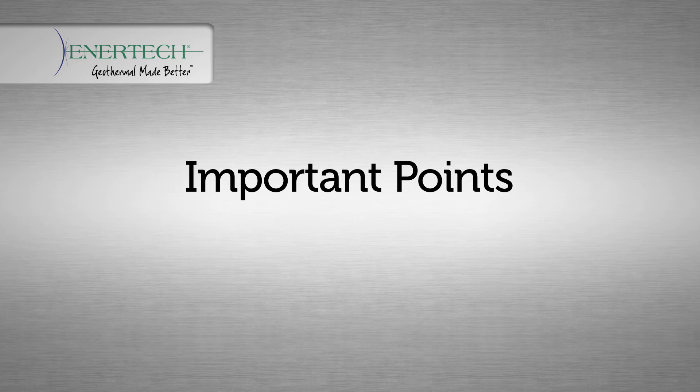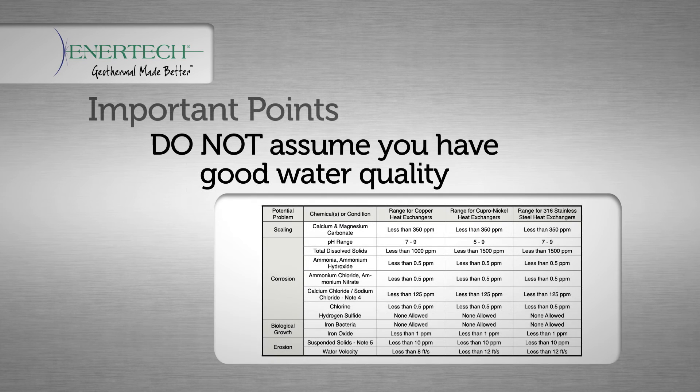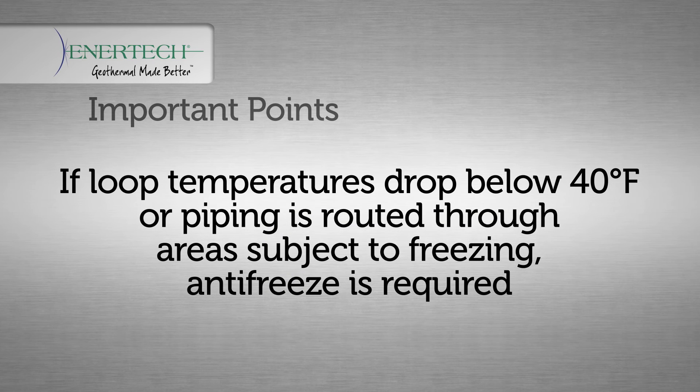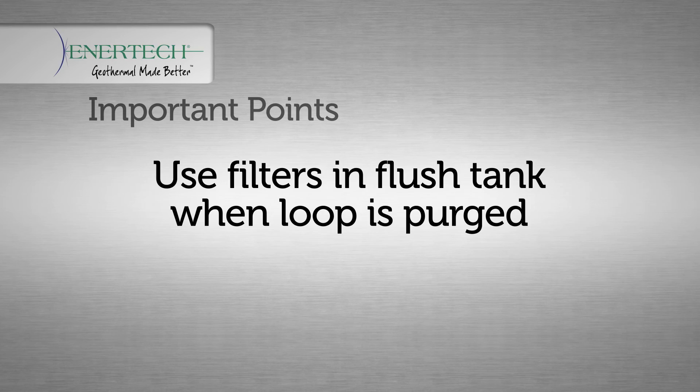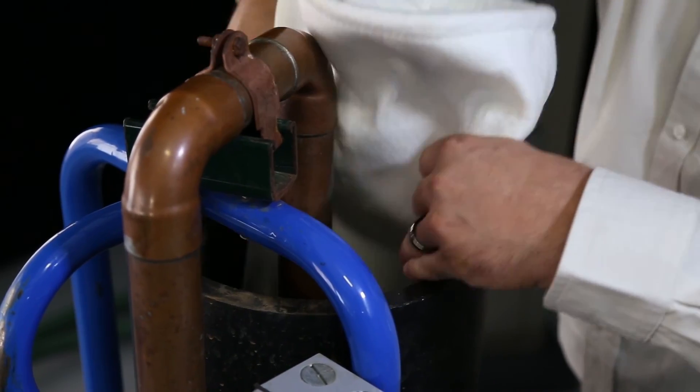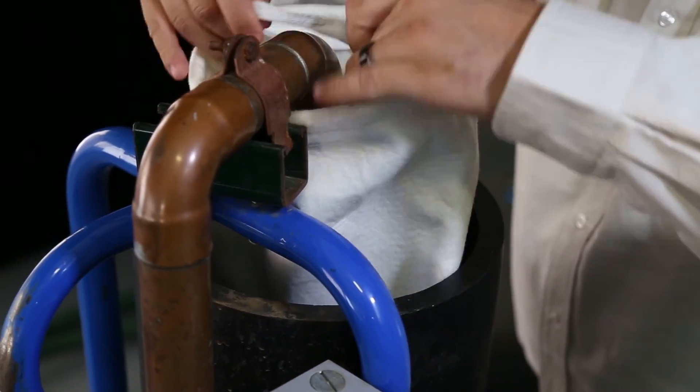Some other important points. Don't assume you have good water quality. Water quality should be tested and compared to the installation manual water quality guidelines. In areas where minimum entering loop temperatures drop below 40 degrees or where piping is routed through areas subject to freezing, antifreeze is required. Loop debris is particularly tough on pumps. We strongly recommend using filters in the flush tank while loop is being purged.